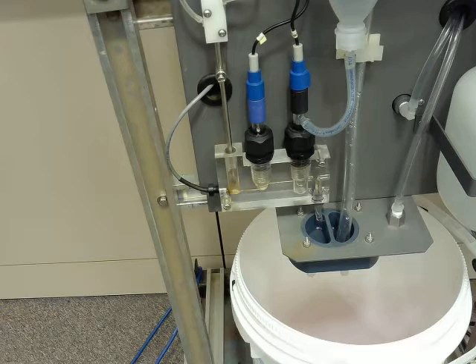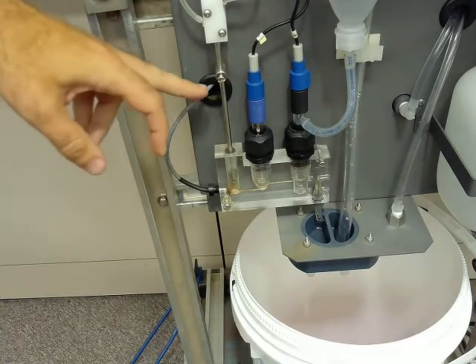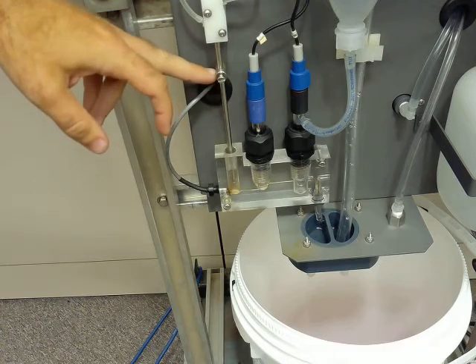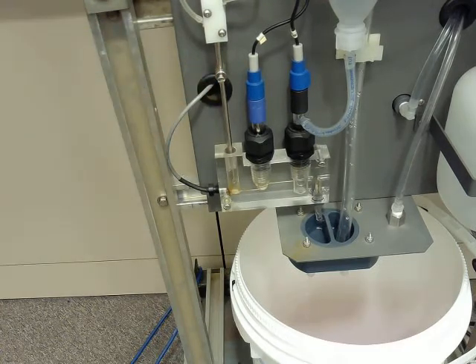The other thing with interference is this earthing tube serves a purpose, being metal and being grounded. Any static charge that might build up as our sample's flowing through the tubing and the components and things like that will get grounded out, and that'll make sure that that doesn't interfere with our electrical signal at all going from our electrodes. Just because it is a sensitive signal, obviously, and we're looking at such a small amount of sodium that it doesn't take much to cause an interference.